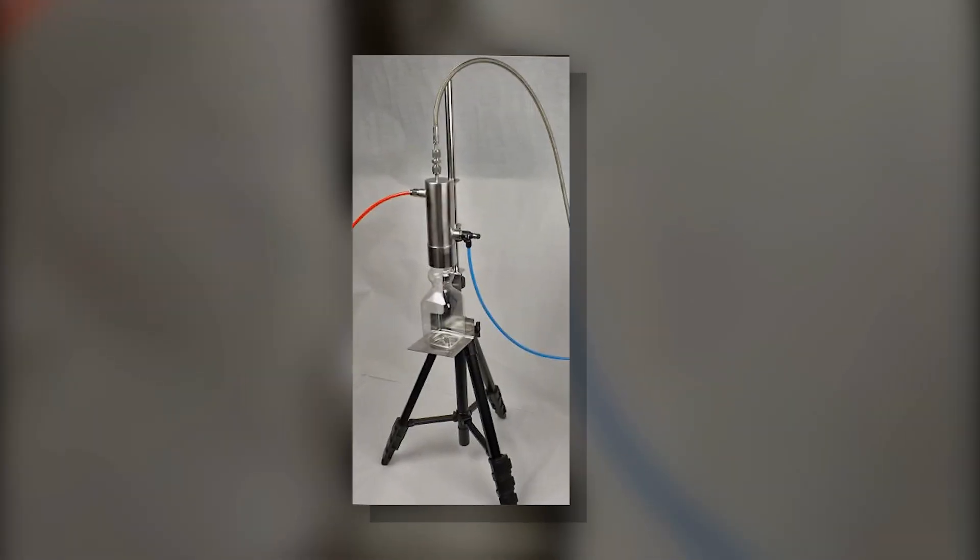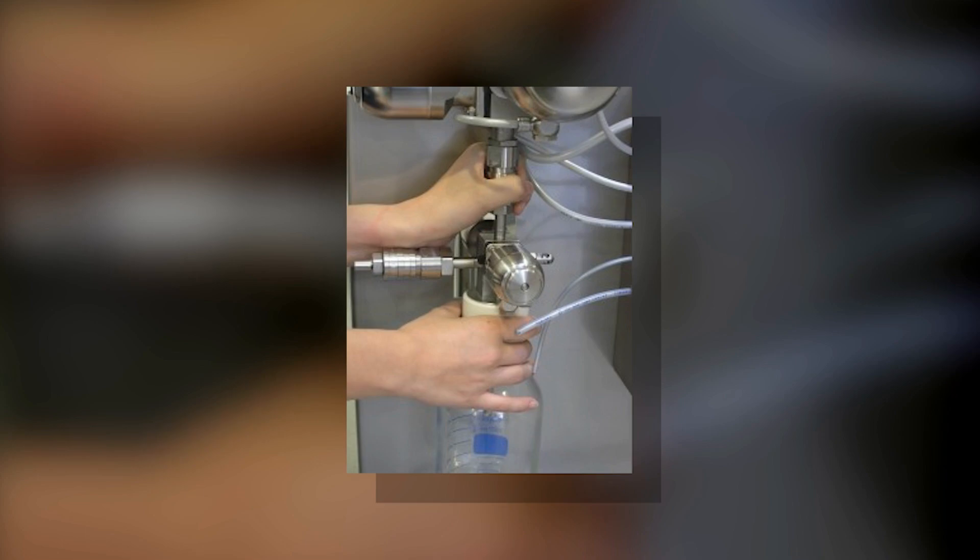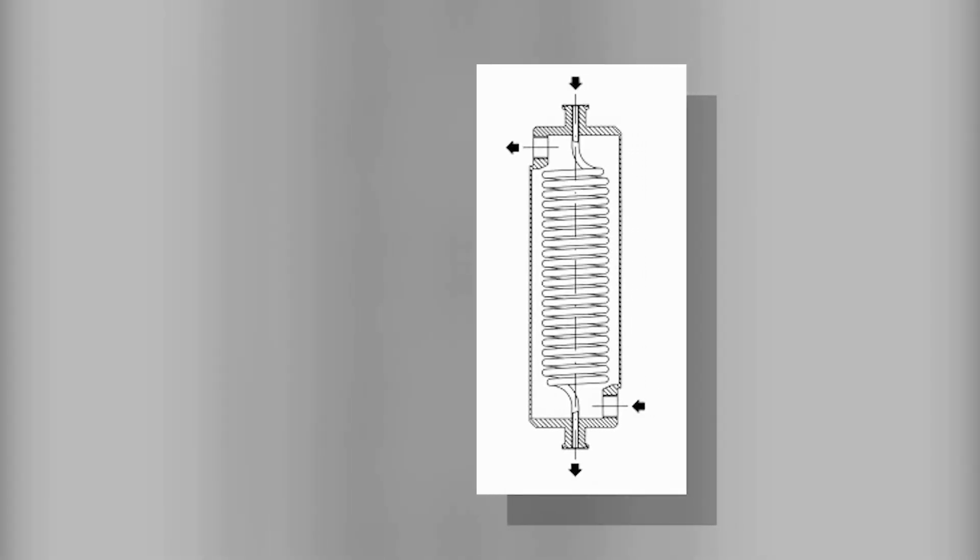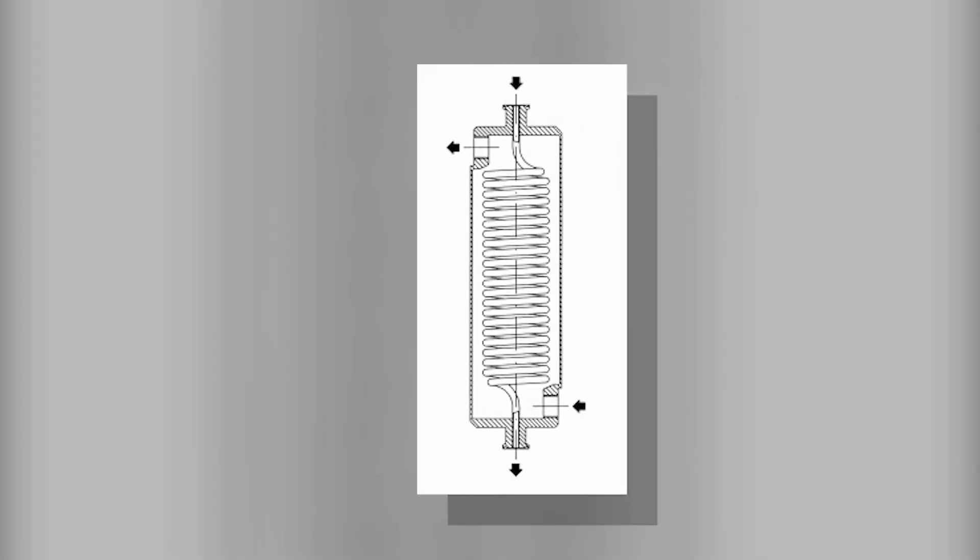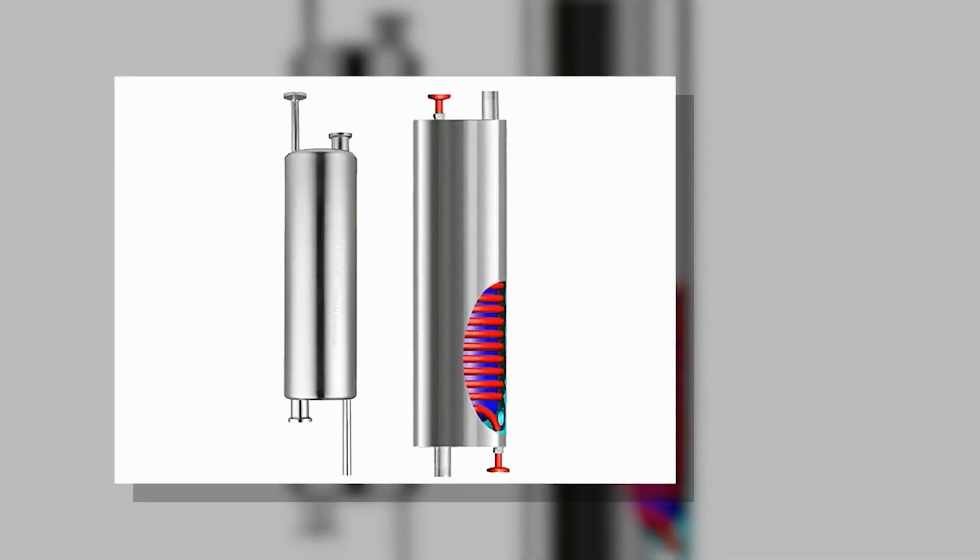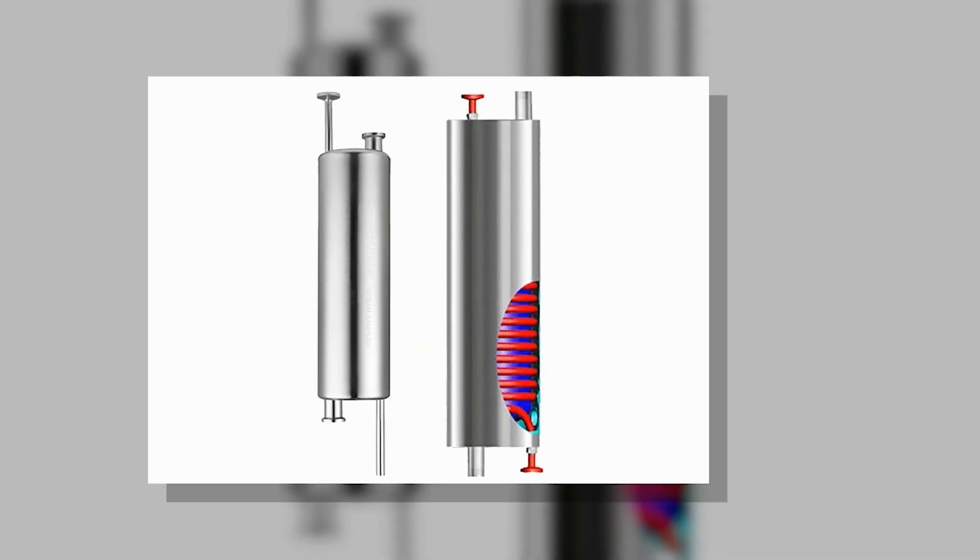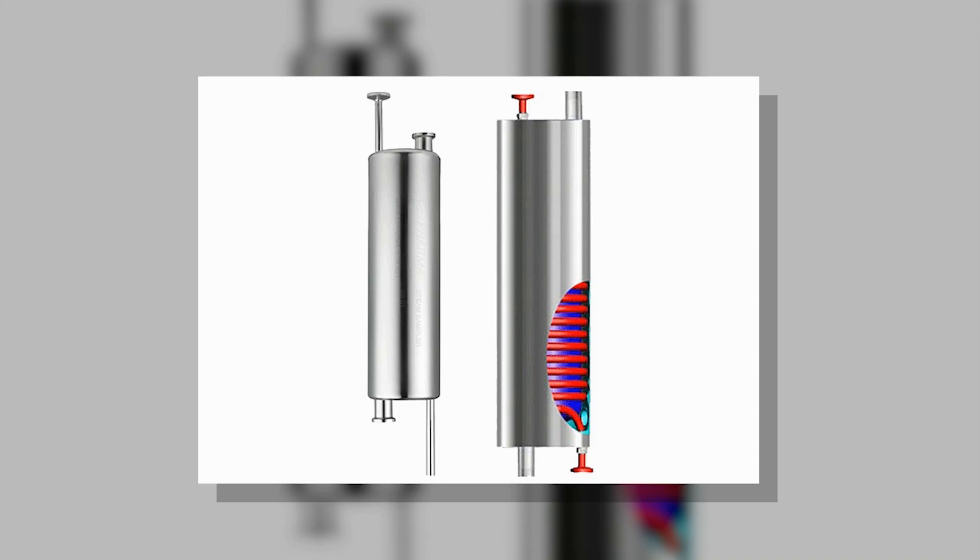The current sampling practice is manual, requires connection to cooling utility systems, and has exposed hose connections providing safety risks to the operator. Coil heat exchangers are also more susceptible to cross-contamination potentially affecting sample integrity.